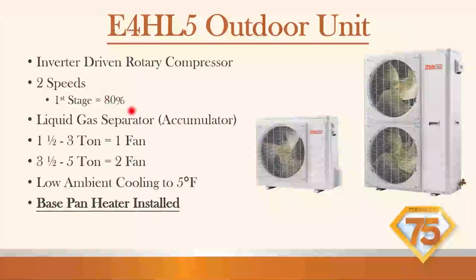I want to hit this real quick because this is what I've seen in the field. Y1, Y2. So we have a Y1 80% compressor. Y2 will be 100% compressor. On their indoor airflow air handler, Y1 will be 80%, Y2 100% airflow. Okay, what happens when the thermostat sends out for a second stage call? Now you have Y1 low speed energized, and now you have Y2 100% speed energized. What happens is it goes to the air handler and ramps up the fan speed to 100%.